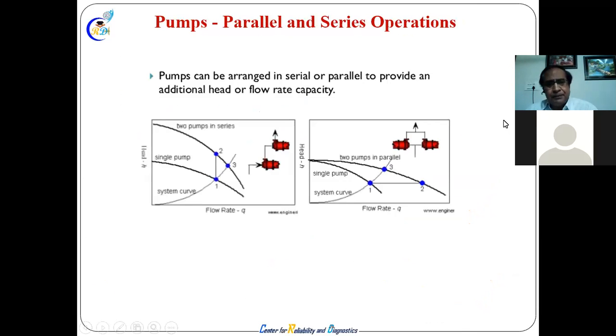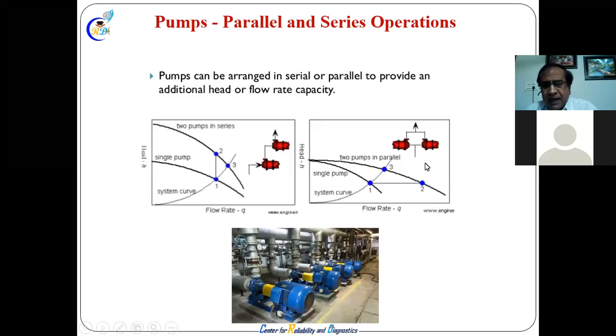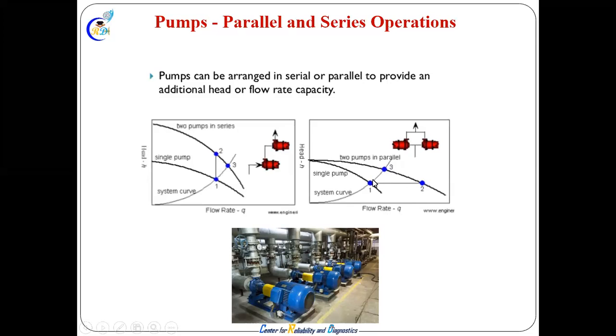And pumps in parallel, you can see pumps in parallel. When you want more flow, put more parallel pumps. But we will compromise a certain amount of flow, because if you put two pumps, you get almost double here in a parallel system. This is the parallel system curve, H versus Q. This is the parallel system curve. The two pumps, 1 and 2, one pump is only here. This is the single pump. This is two pumps in parallel. With two pumps in parallel, you will see double flow. But in practice, you won't get it.